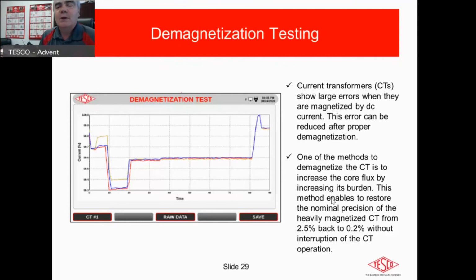Now, some field equipment, and the shop equipment is very, very good at doing this. Sometimes in the field you have to do it more than one time to actually get the unit demagnetized. But often, if you see bad results on a CT and the CT is not obviously damaged, very often the bad results are actually just the result of magnetized CTs. So it is something that should always be done. It's always a best practice to do it anytime you are working with CTs, whether it is in the field or in the shop. You should always demagnetize them at the end of the test.